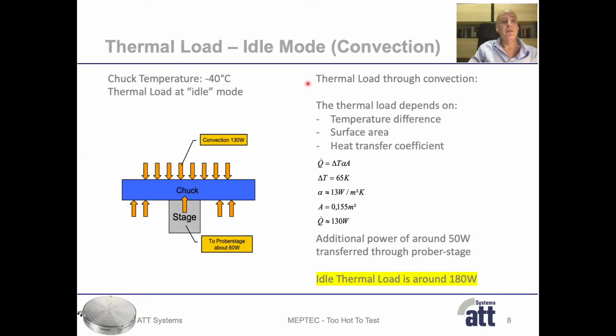So, where's the thermal load coming from? In idle mode or standby mode, we have a thermal load through convection. Let's assume that the chuck temperature is at -40 degrees C. The thermal load through convection depends on the temperature difference. In our case, the delta T is 65 Kelvin, assuming that the ambient temperature is at +25 degrees C. Then the heat transfer coefficient and the surface area. So this gives us a thermal load through convection of around 130 watts.